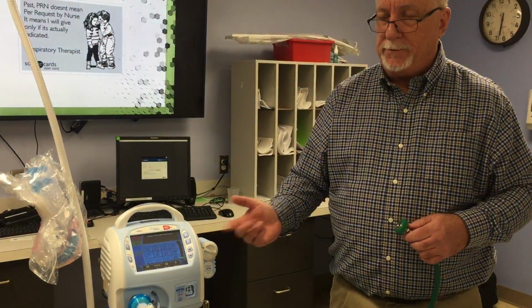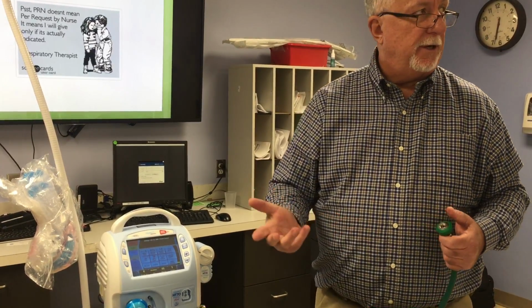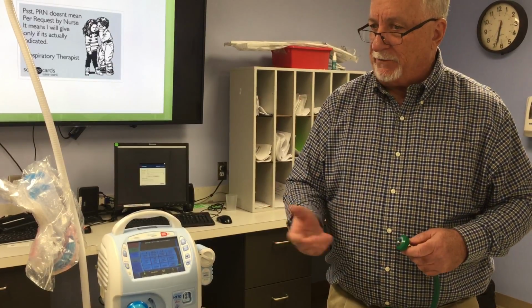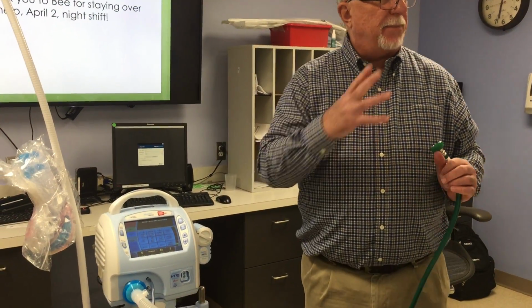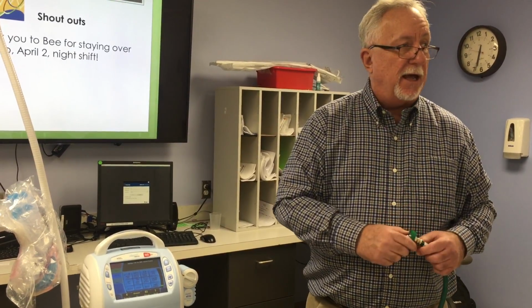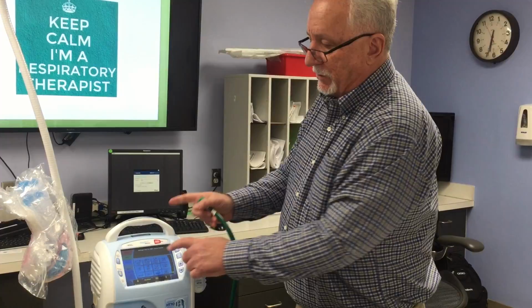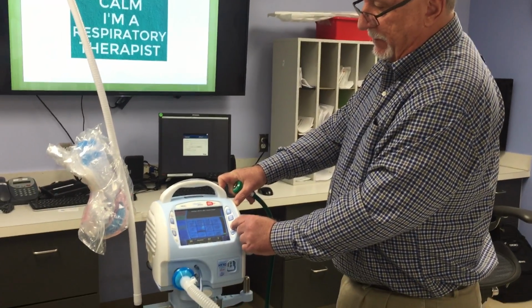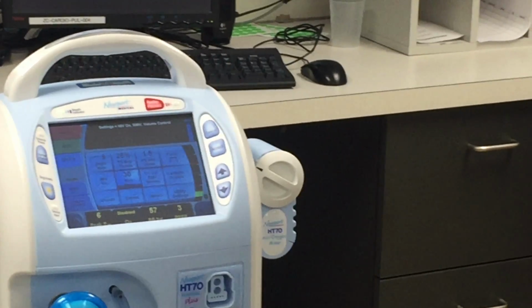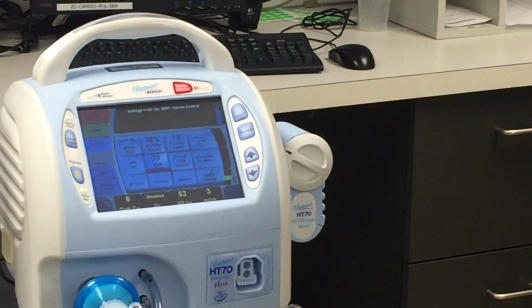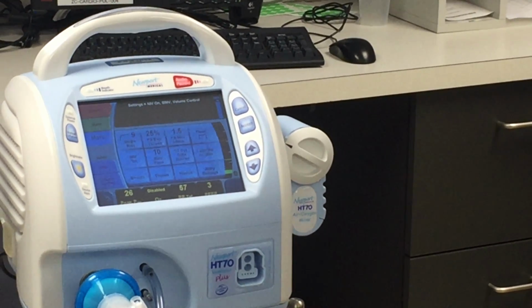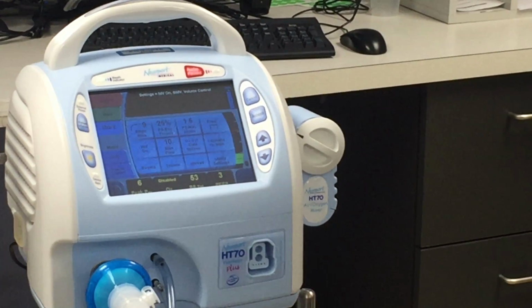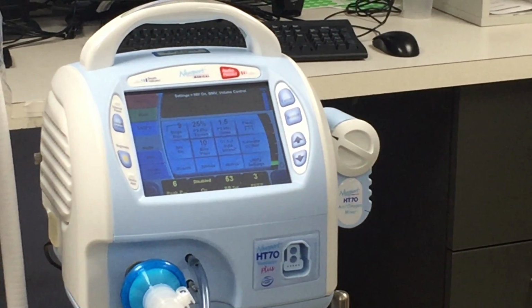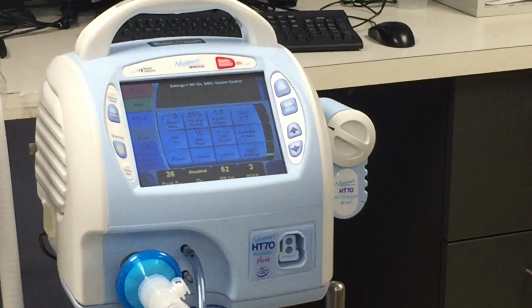Again, you would put it into spontaneous mode. You would set your pressure support and your PEEP, which would be equivalent to your IPAP and EPAP, and that's how you would set it up in non-invasive. What's a good leak range? I would start out at 10, and just depending on what interface you're using, I would recommend a full face mask if you're going to use it non-invasively, not a nasal mask. But you can go up to as high as 30 liters per minute if you need be. Okay, with your leak. And again, it's not like a V60. You know, it's pretty basic, non-invasive for patients. So it's not going to be for all your patients that you would use that, but you do have that capability to use it with it.